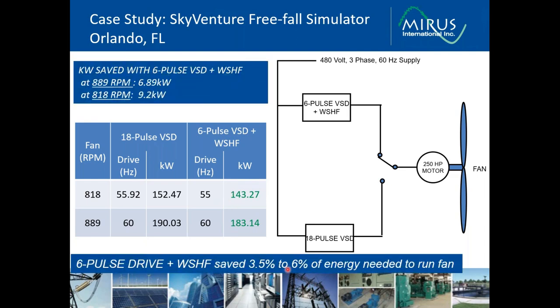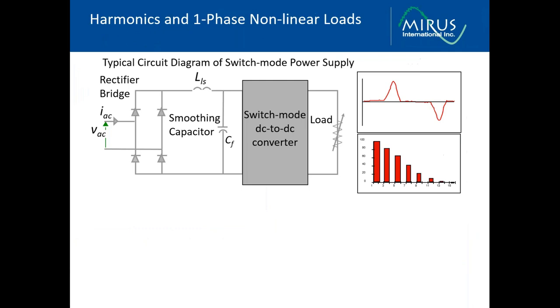So when you look at this, at the higher speed, there was a 6.9 kilowatt reduction. At the lower speed, there was a 9.2 kilowatt reduction, so a 3.5% savings at the higher fan speed and as much as a 6% savings at the lower fan speed. So, a substantial reduction, and of course the customer did decide to go with the passive solution in the end.